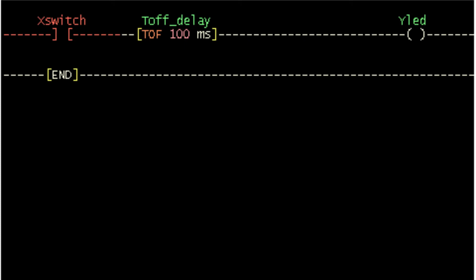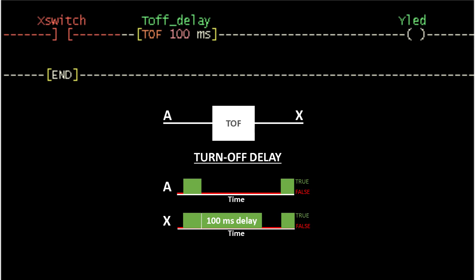Now let's go on to the turn off delay timer. The turn off delay timer is identified by TOF, the time interval, and the variable name. When the timer input signal goes from true to false and remains false for the specified time interval, its output is delayed for that time interval before it will become false. The output will become true once the input changes to true. If the input goes true before the specified time interval is completed, the output will remain true.